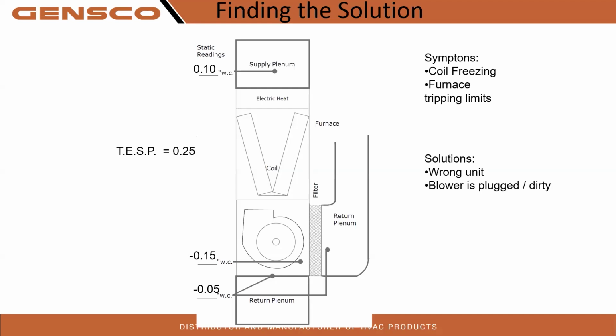Blowers plugged or dirty, so it's not ramping up. Oh, with the TAM9, TAM-X's, this is critical too. If we do not have enough air, it will not fire up heat strips. We'll get a heat strip alert. So keep that in mind.